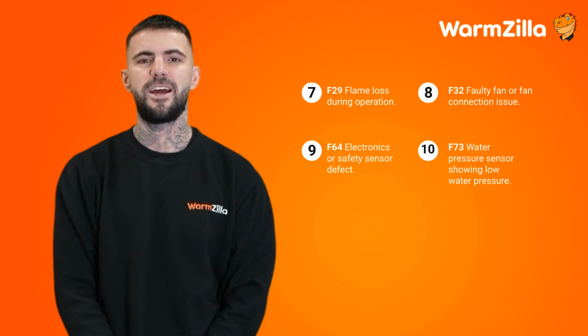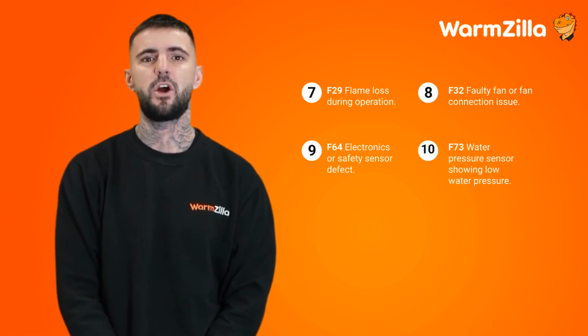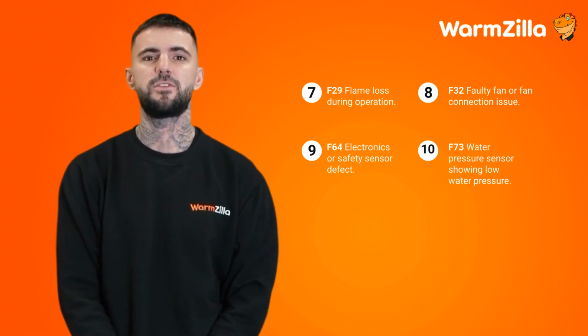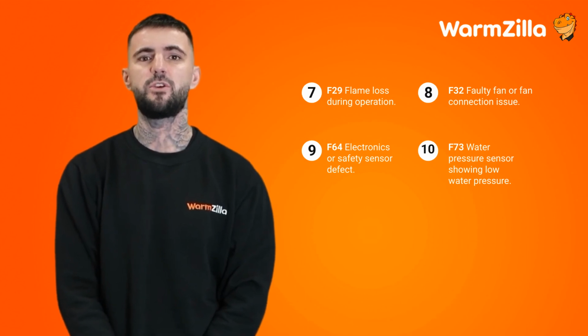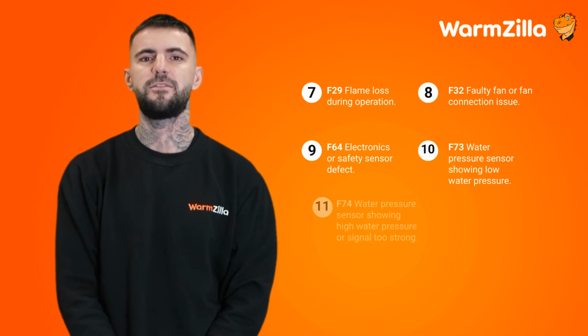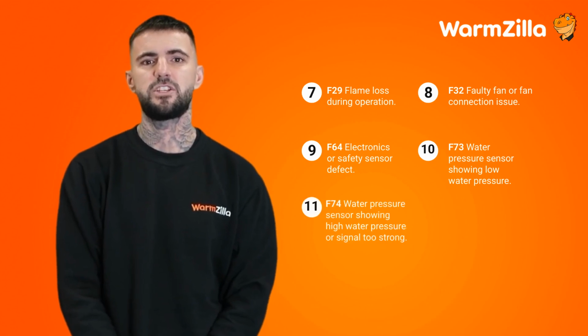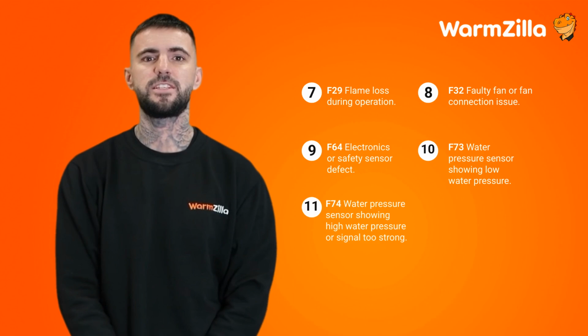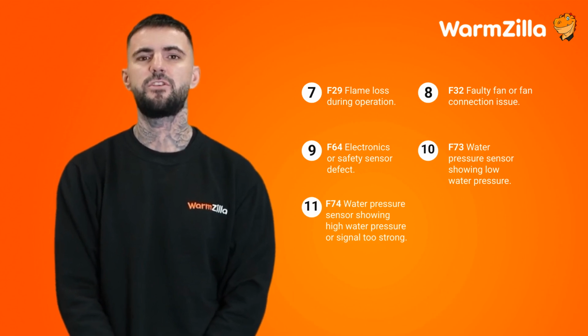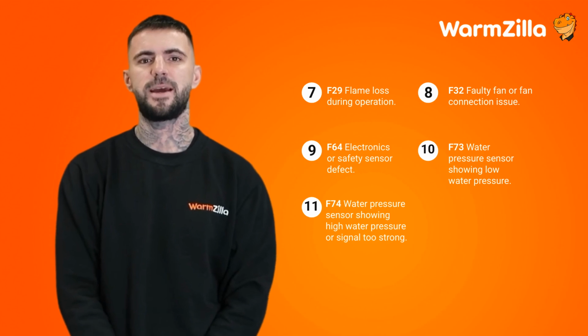F73 means that the water pressure sensor is showing low water pressure. Just refill your system, check for leaks, and ensure the sensor is functioning. F74 is the water pressure sensor showing high water pressure or the signal is too strong. You'll need to release the excess pressure, check the expansion vessel, and inspect the sensor.